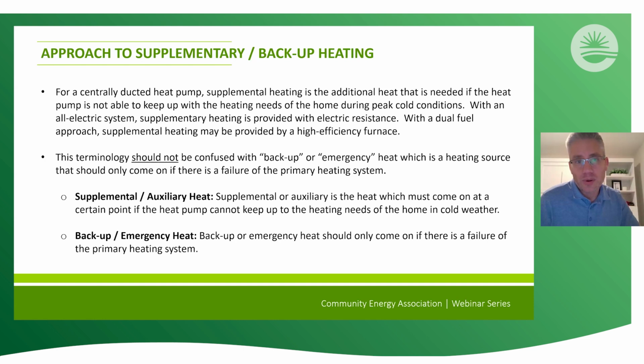And then with dual fuel approaches, the supplemental heating would be with a high efficiency furnace. One important distinction between the all electric and the dual fuel is that with the all electric, as we were mentioning, you can stage on to really supplement the heat pump when it can't keep up. But with the hybrid dual fuel solution, it's really an on or off situation, where either the heat pump's working or the gas furnace. So you don't run both of them at the same time.